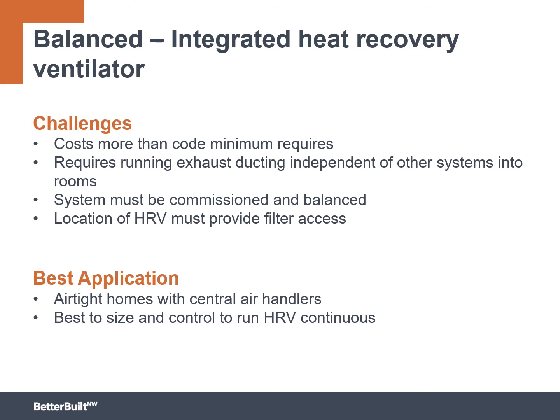And of course, we still have that same challenge of where do we put the heat recovery ventilator to make sure we have access to the filter and maintenance. So this is a pretty good application when you have a fairly tight home that already has a central air handler. And it's best to make sure that you size and control to run the HRV continuously, regardless of how often the air handler fan moves. So again, some challenges and some good applications for this strategy.